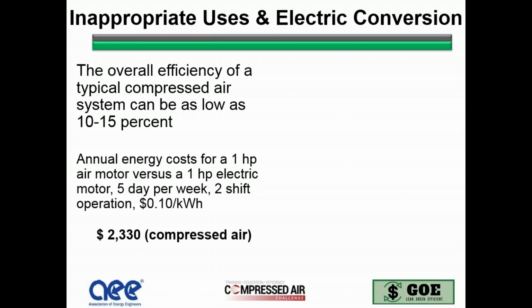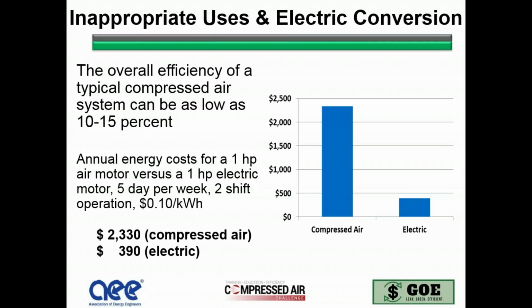for the compressed air, it's $2,330 a year. For the electric, it's $390. So you can see there's a great difference, because of all of the losses in the system, most of those coming from the heat of compression that you have in a compressed air system. So really looking at what you can change, and where and how you're using the compressed air, is an important part to look at.